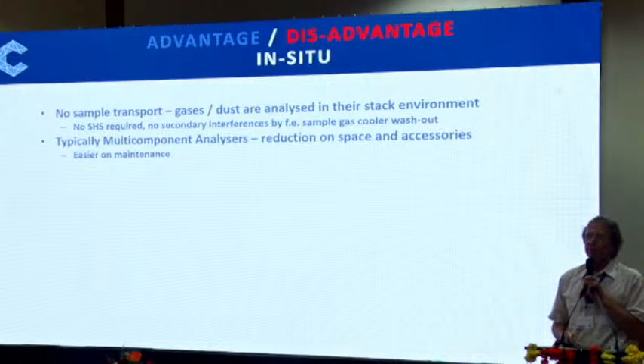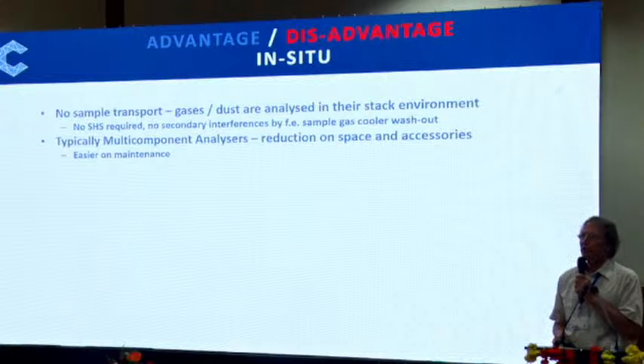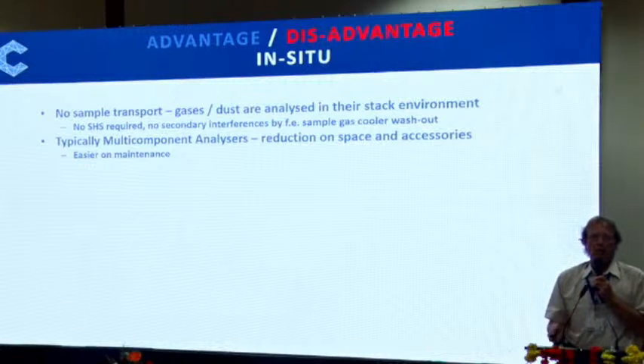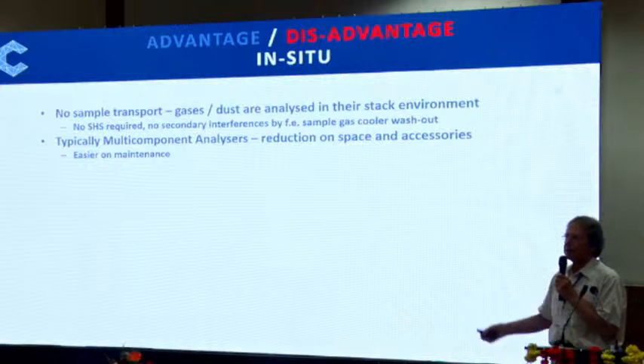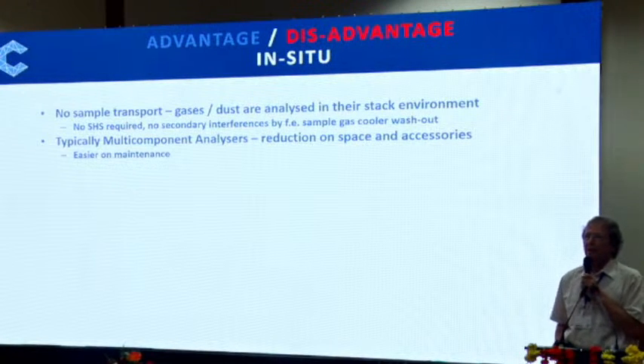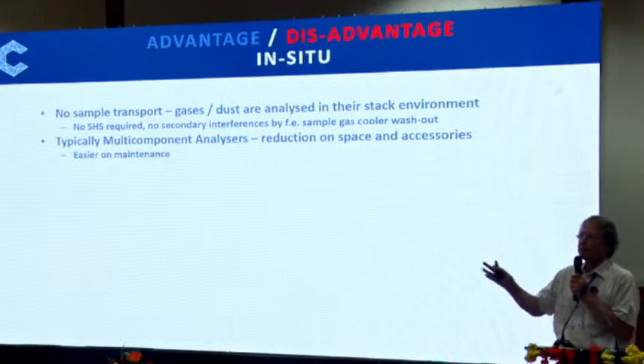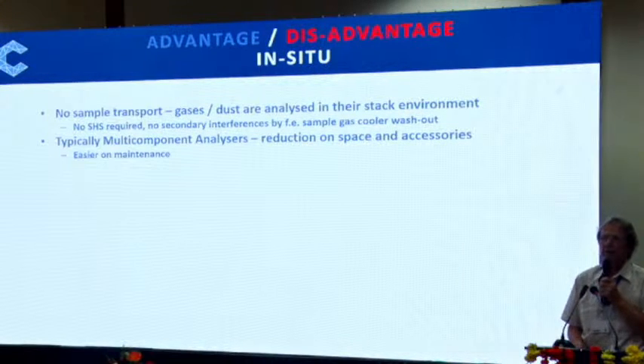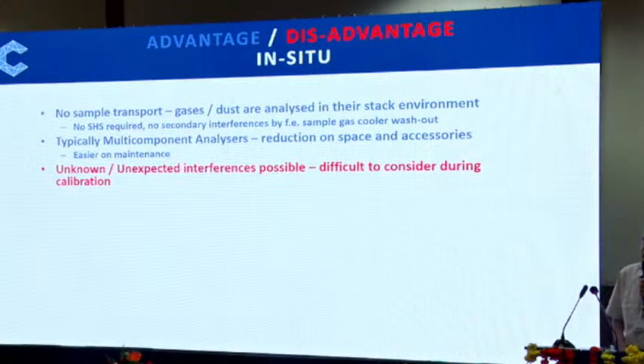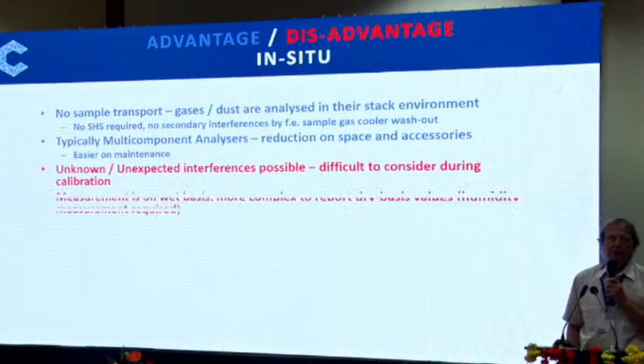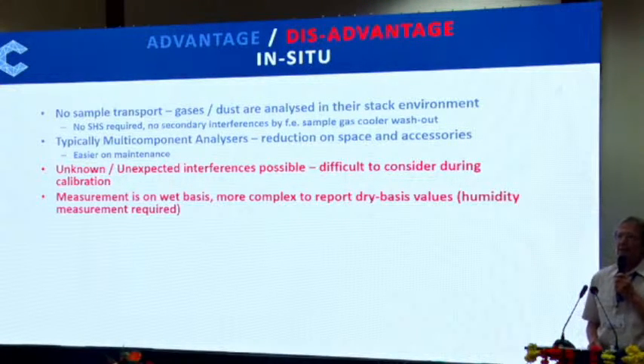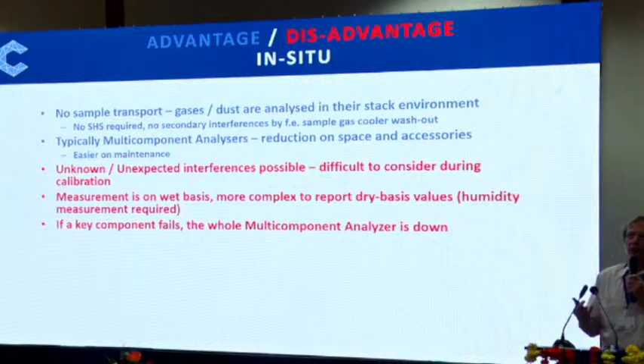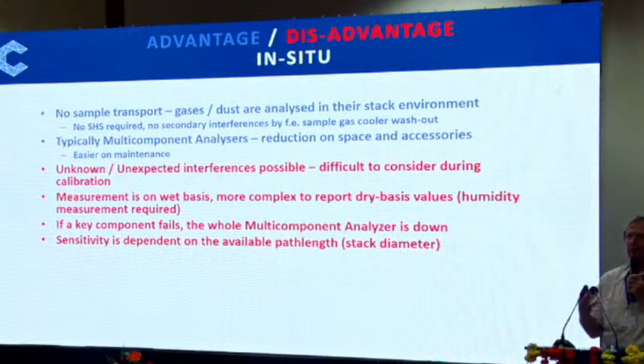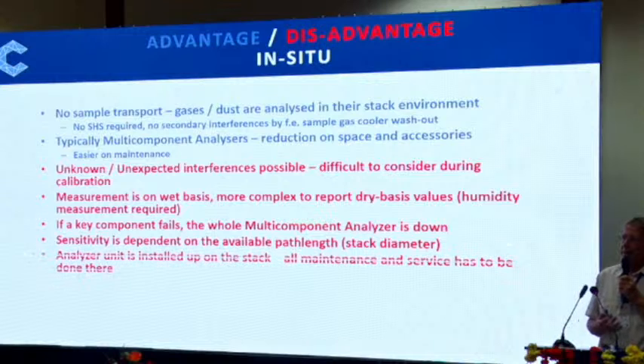Typically, there are multi-component analyzers, so typically in a multi-component analyzer, if one component fails, then I lose all data. If I have individual analyzers in a CEMS system, if my NOx analyzer fails, I still get my CO and my SO2 and oxygen, etc., giving me data. Disadvantages, there might be interferences inside the stack, which I don't know. Interferences in the wavelengths with components I don't know.